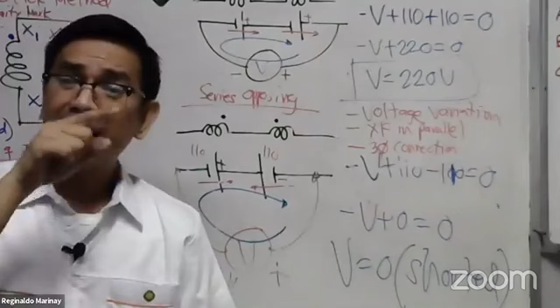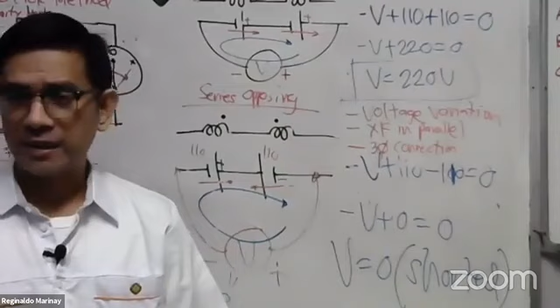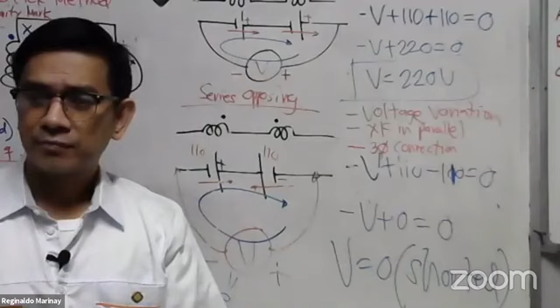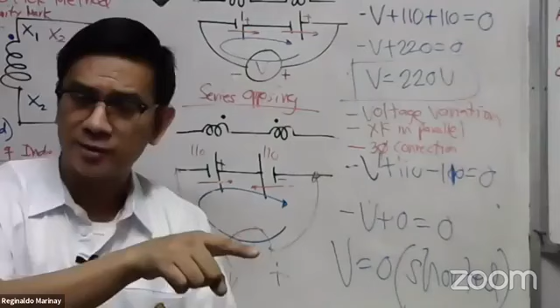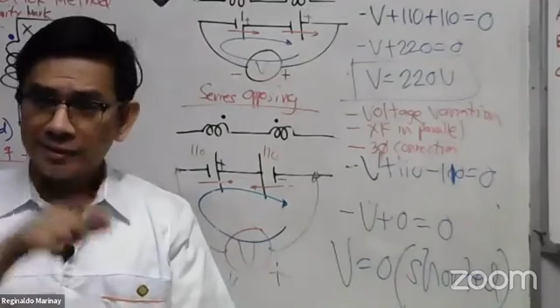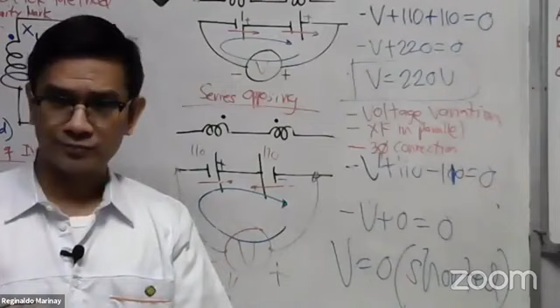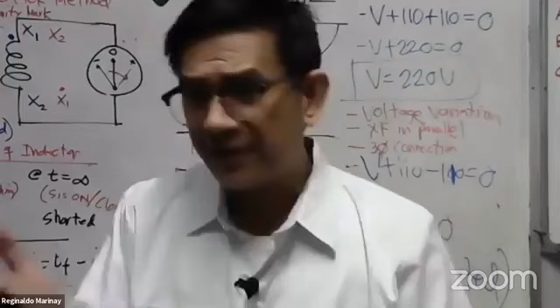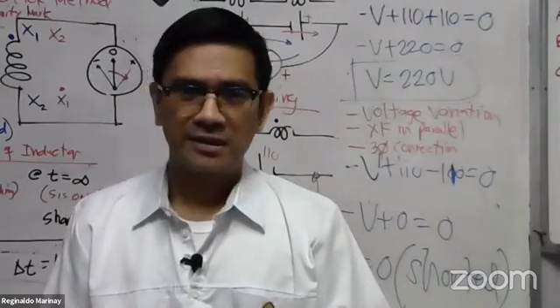But if you are to connect transformers in parallel, it should be H1 to H1 of the other transformer. Imagine you have two transformers: X1 of transformer 1 must be connected to X1 of transformer 2, X2 of transformer 1 must be connected to X2 of transformer 2. Well, if you are making a three-phase connection, that's another thing. I have some diagrams of three-phase transformer connections. Maybe we could share that with you next meeting, partner, if you want to explore this.